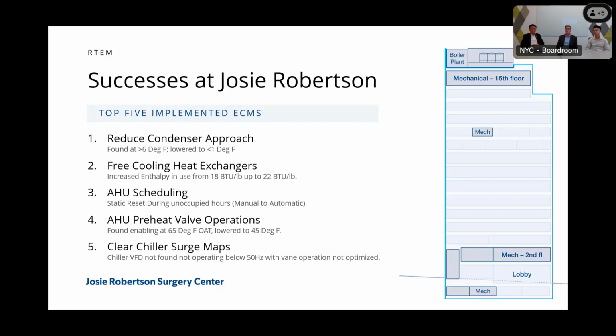And the condenser approach, we catch condenser approach in most buildings. That's something that occurs naturally here at the Josie Robertson Center. When we first started the monitoring program in June 2017, that was the first thing we called out, because in June, your condenser approach should not be that high. So after flagging it for the site, we actually came on site. We did kind of a review. We checked out the sand filter. After they had corrected the sand filter, we still saw a little bit of an increase. And the site developed a pretty rigorous cooling tower cleaning program to address the condenser approach. This really talks to the partnership that RTEM has with the client and the successes that we've had.